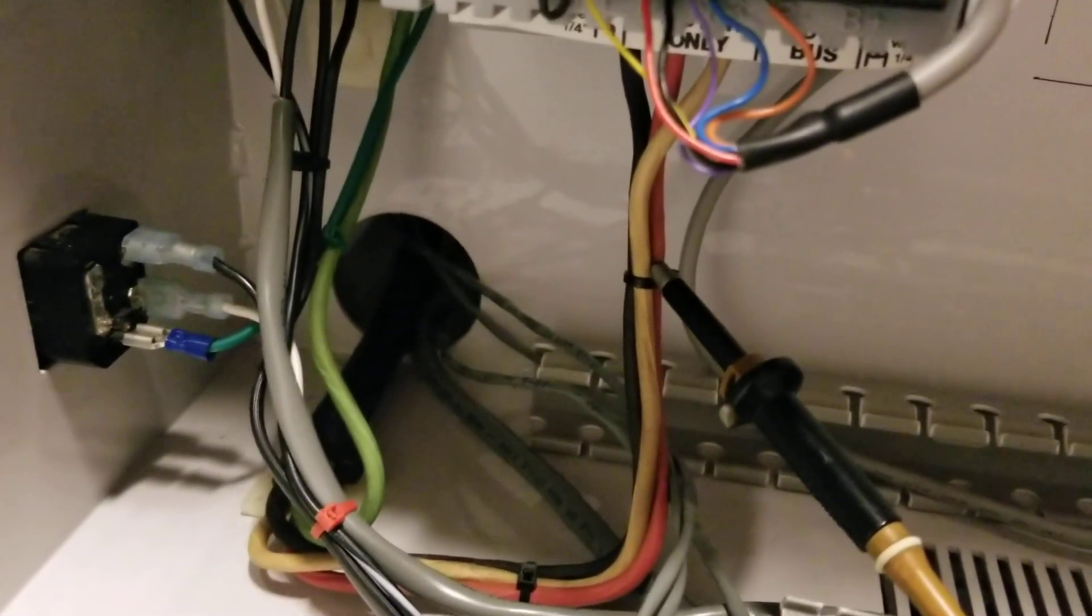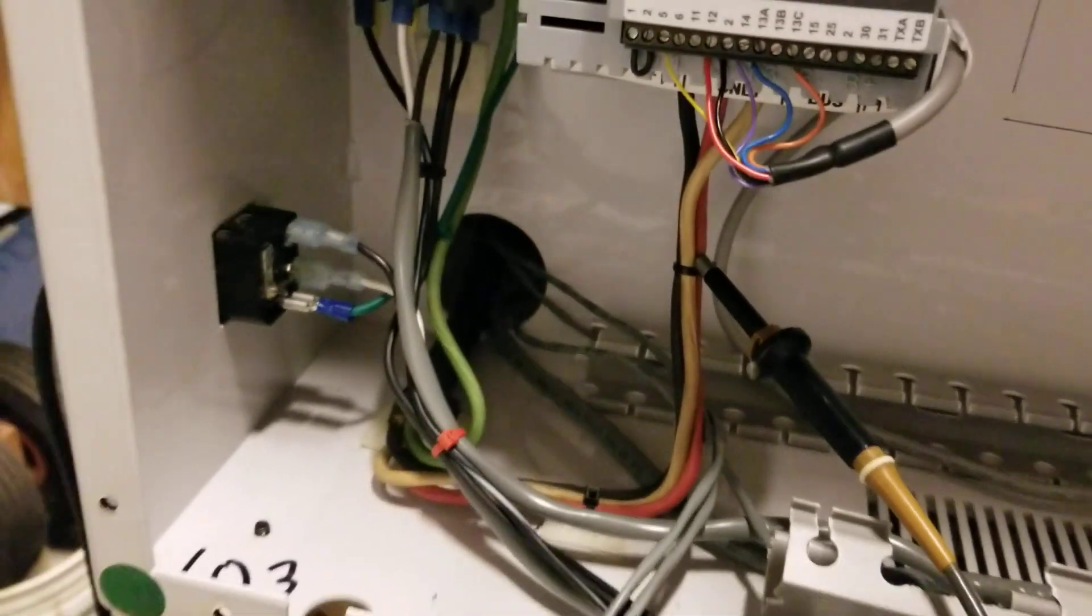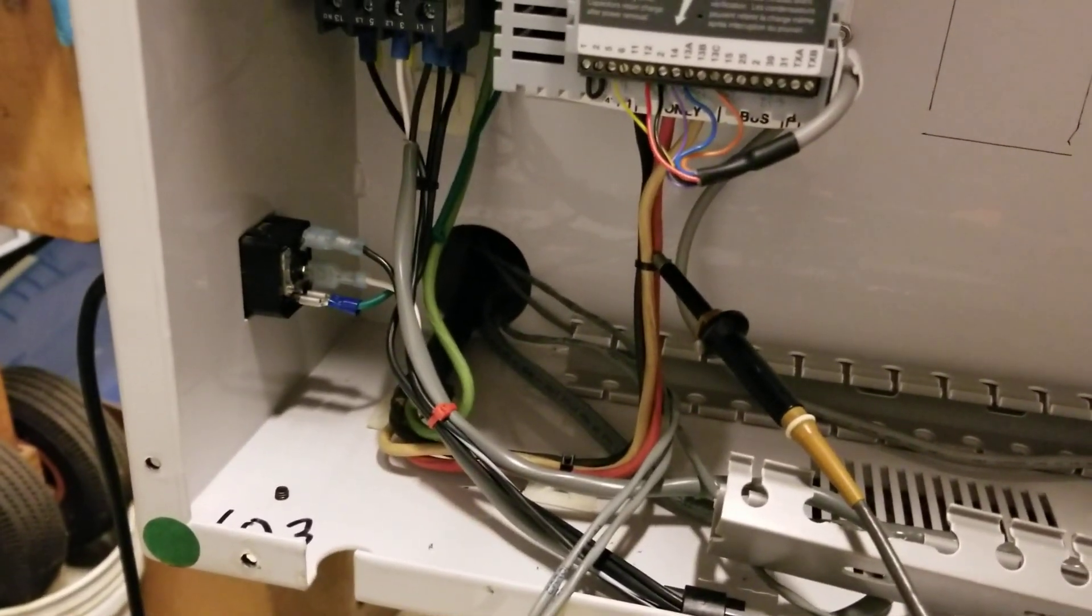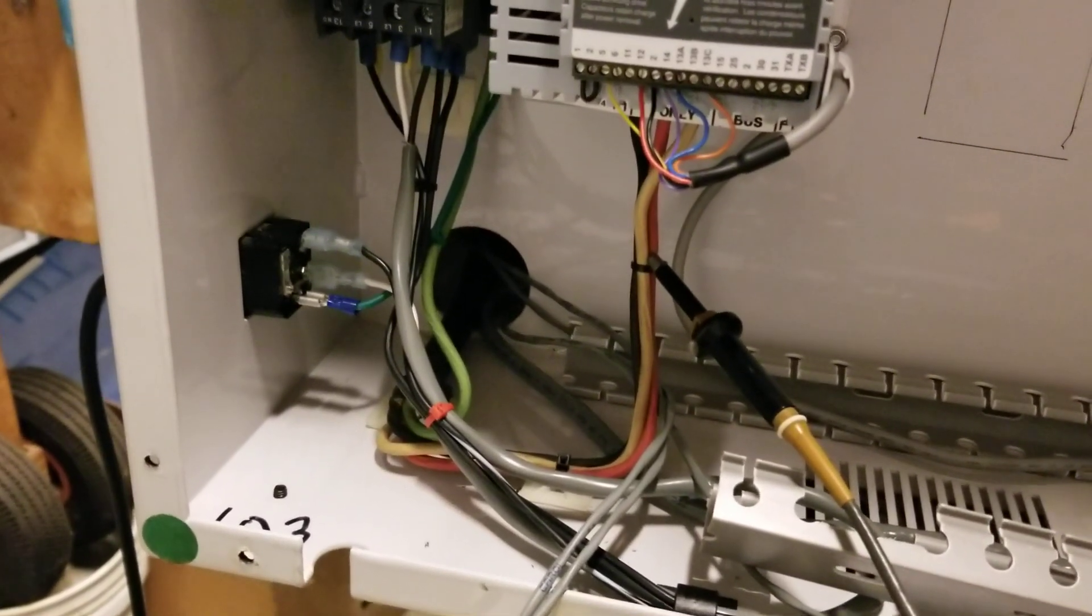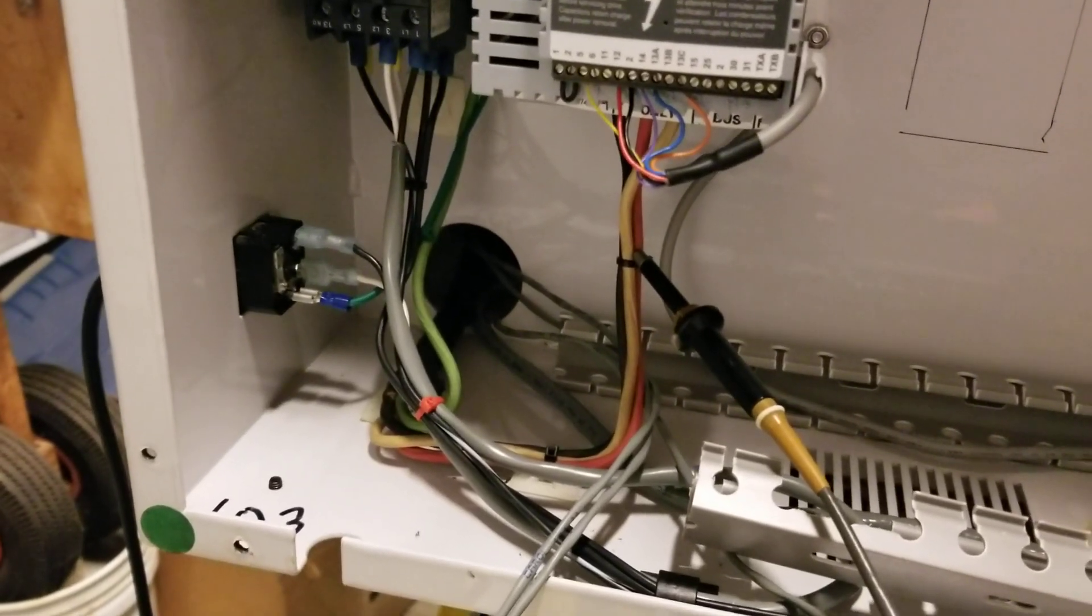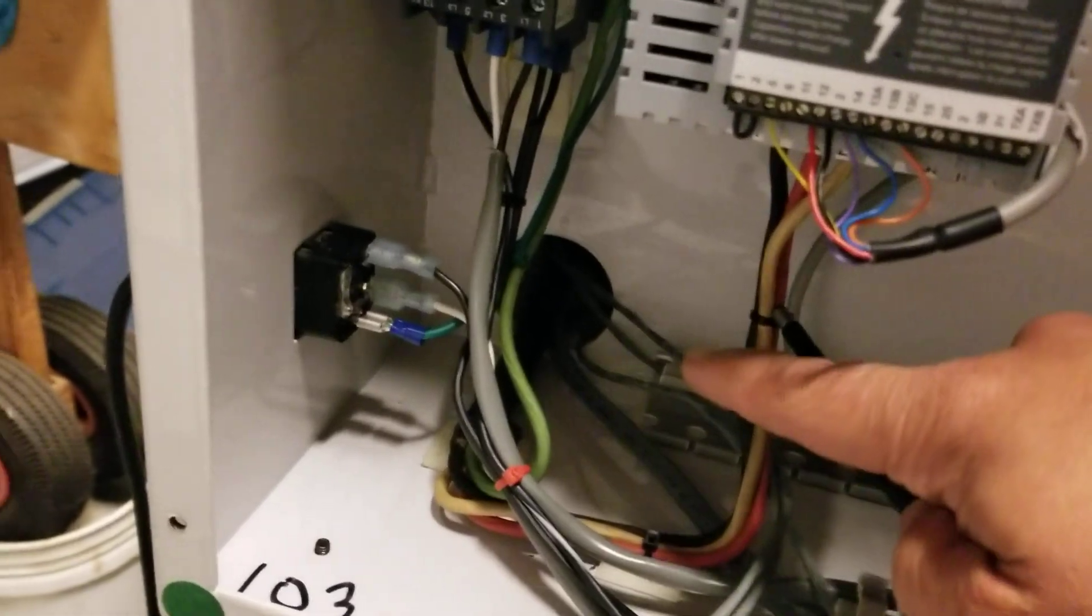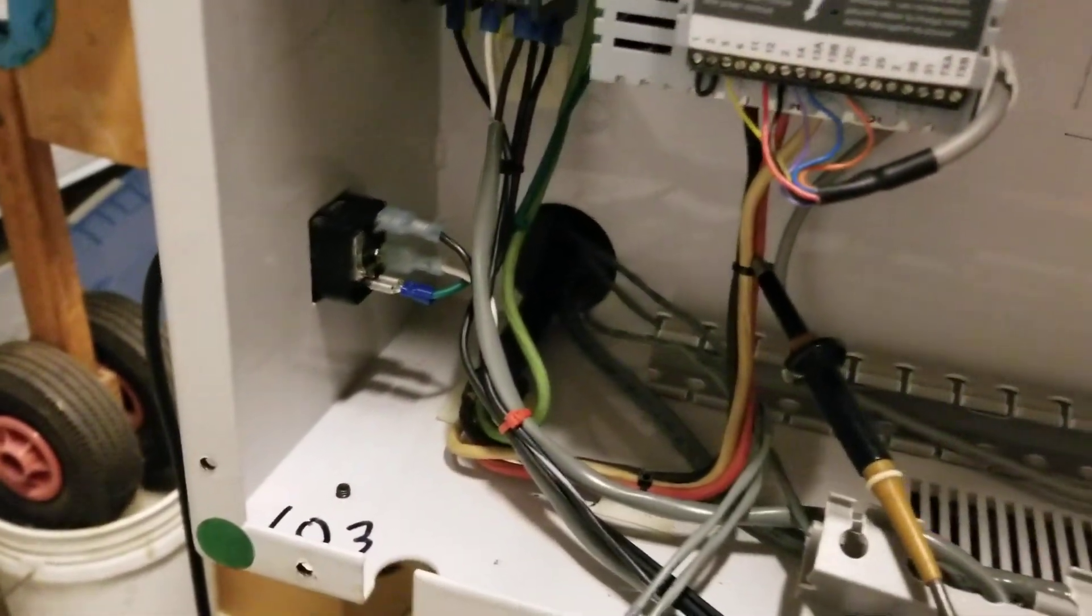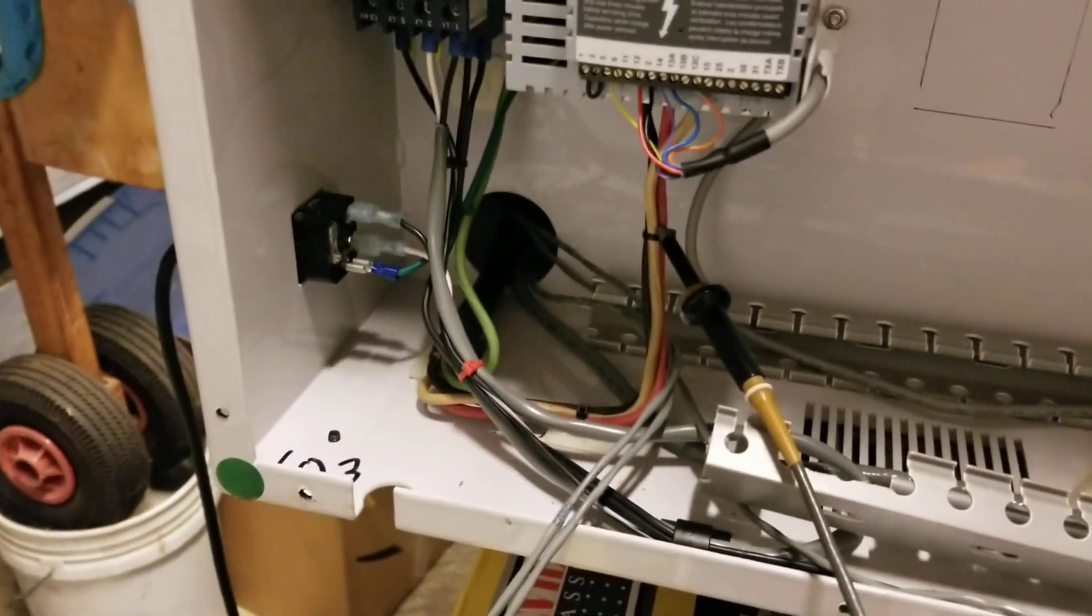That I don't like a whole lot. So I think I'm going to go ahead and swap out this three-phase cable for a shielded one. That should give me a little bit more immunity from EMI. Especially as I run signal wires through this hole into the other side. I don't want any interference there.